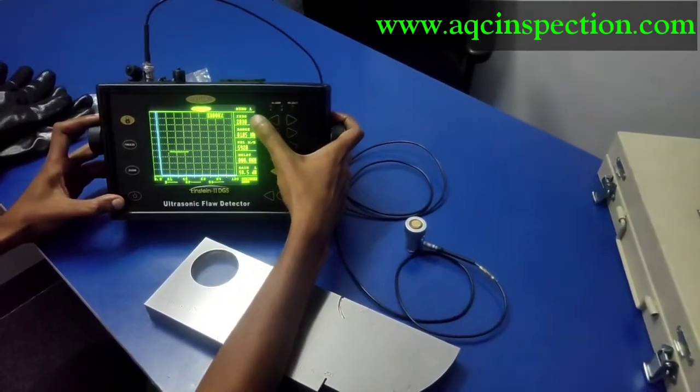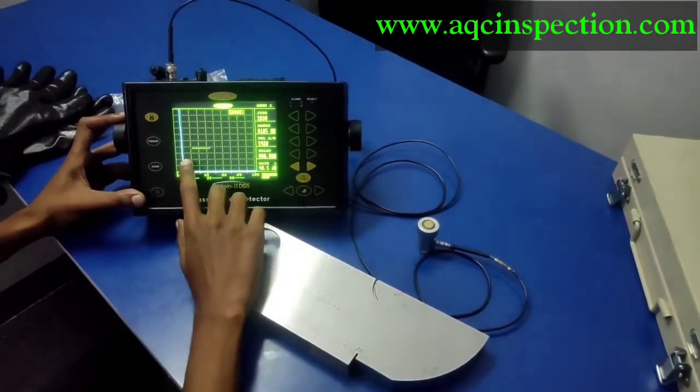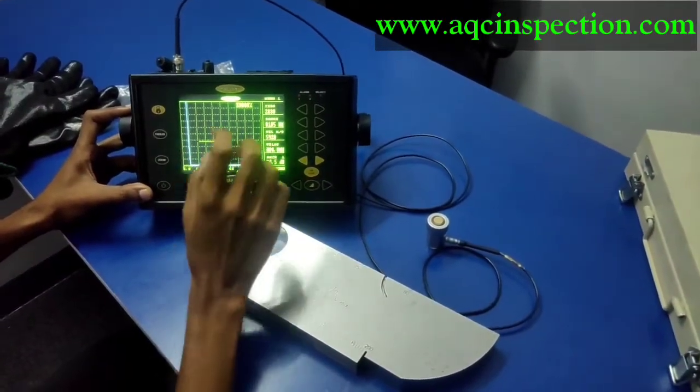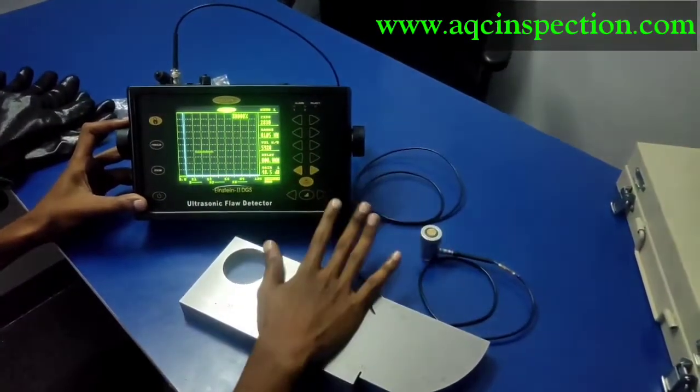This right here is the zero of the probe. We have to calibrate this to 25 mm which is a known thickness so that we get four backwall echoes properly. Once we calibrate this, then we can do the inspection.